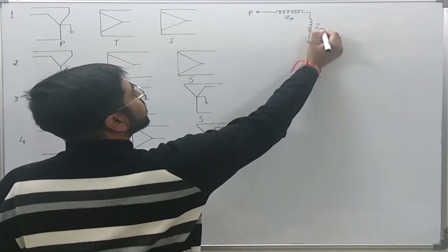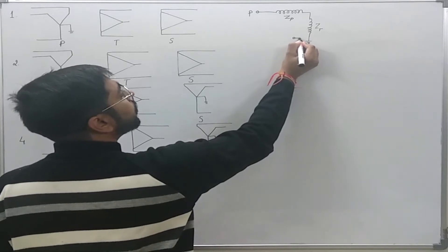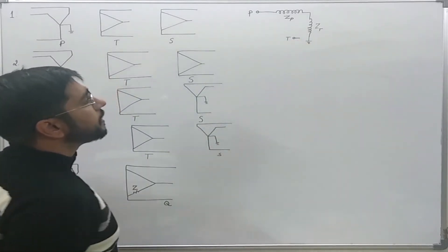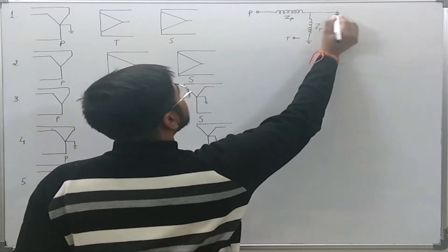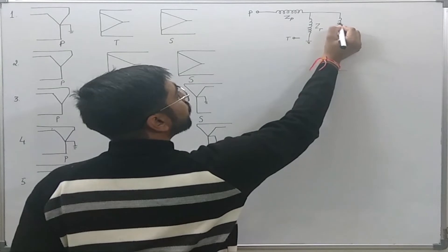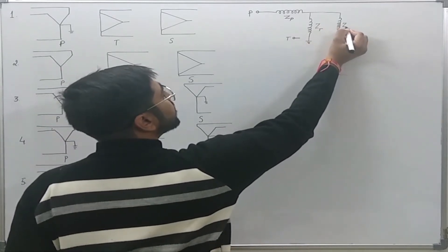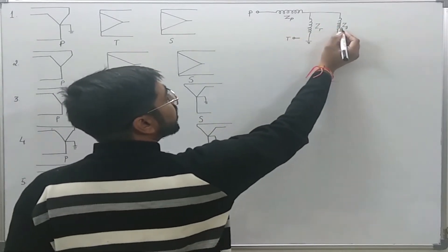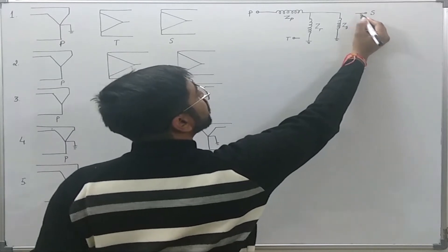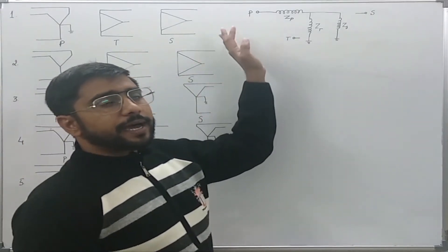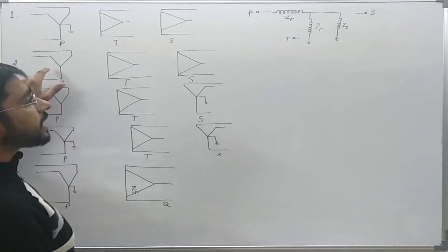The tertiary side will not carry any zero sequence line current on the tertiary line. The secondary delta will offer its impedance Zs to the circulating zero sequence currents; however, these currents cannot appear in the secondary line, so it will be an open circuit on the secondary line. In this way, we can draw the zero sequence network for this kind of connection.